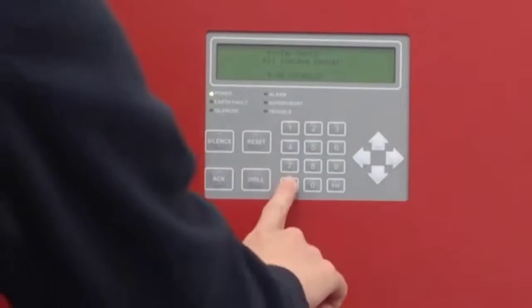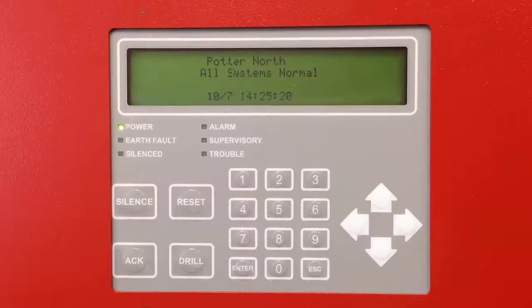The last thing we'll cover is running a fire drill from the fire alarm control panel. Prior to running a fire drill, make sure that the AHJ, or the authority having jurisdiction, and central station monitoring are aware that a fire drill is being performed. Follow all local codes and standards when performing any procedure on the fire alarm control panel.